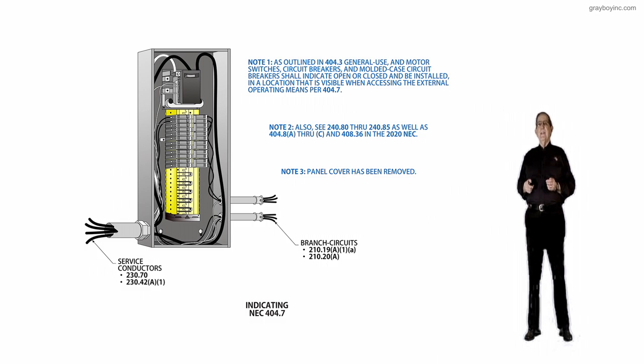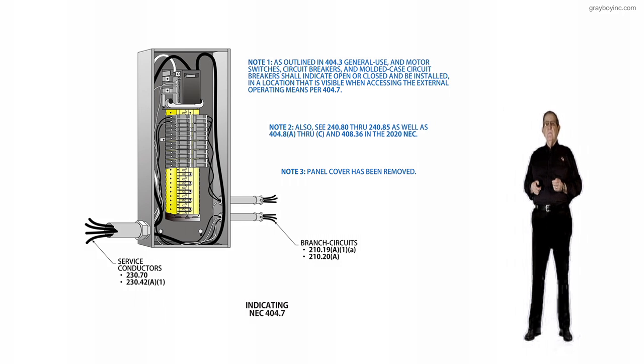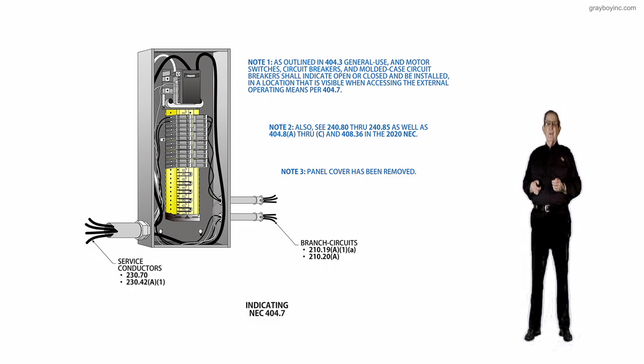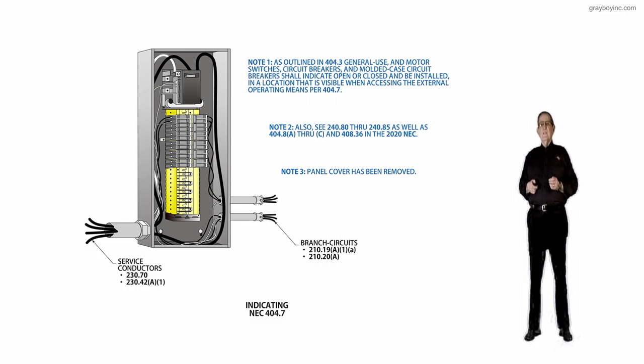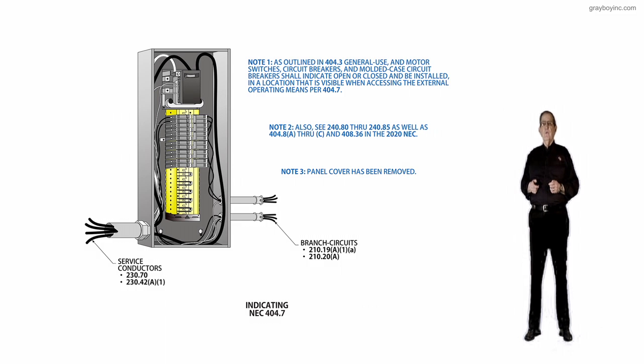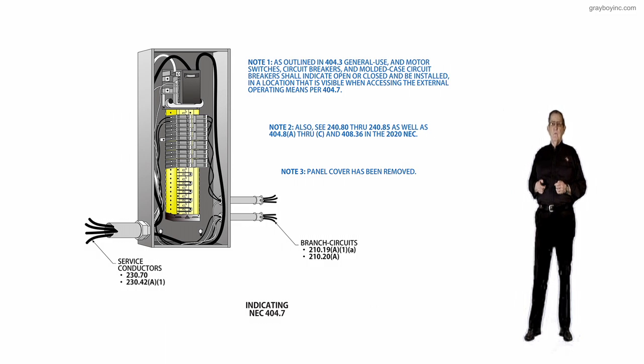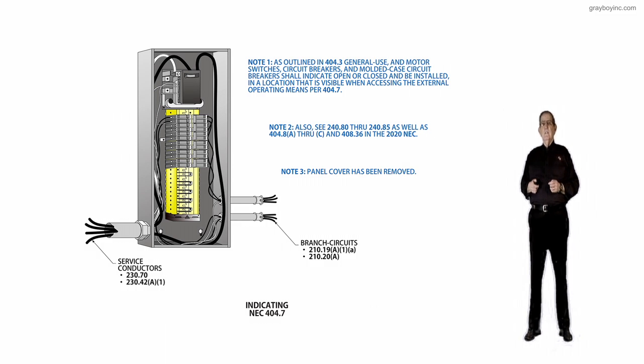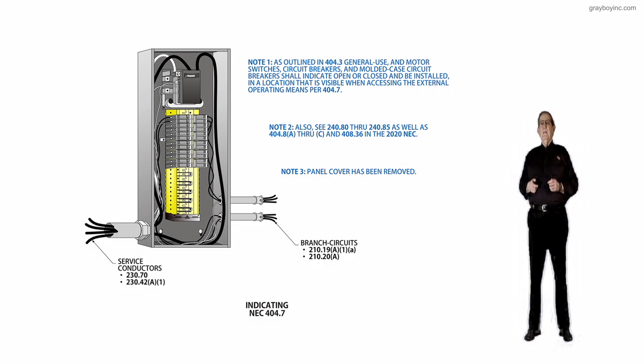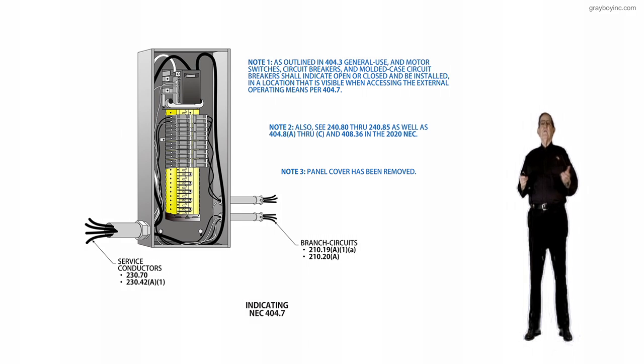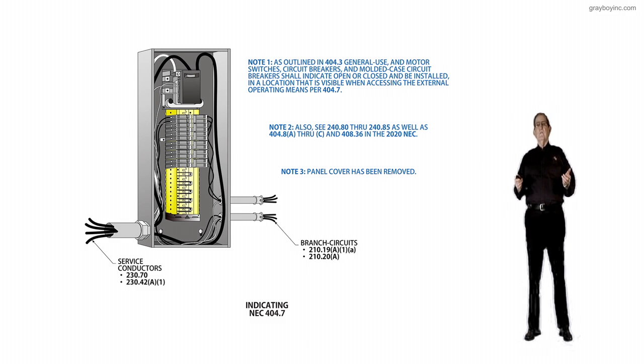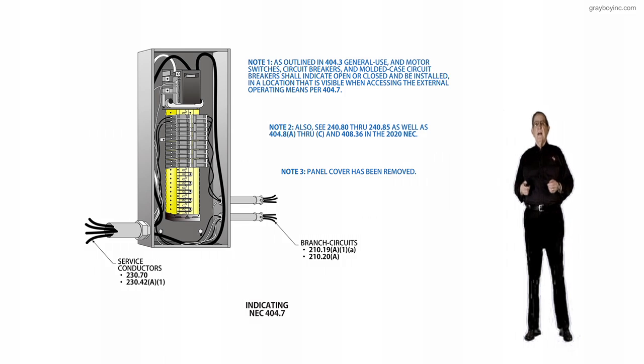210.19A1A is the calculating procedure for the conductors, which contains the 125% rule for continuous duty. And then it's 100% for non-continuous duty or with demand factors, whichever applies.